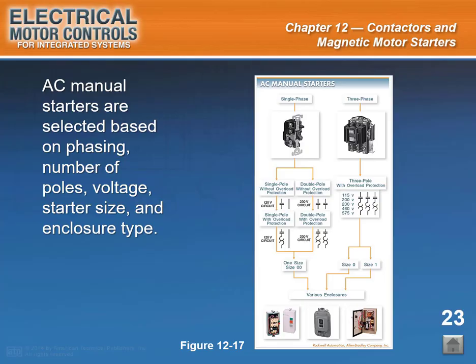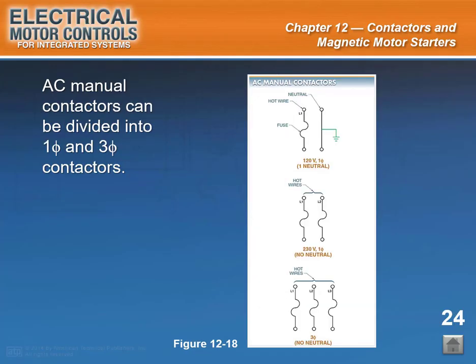AC manual starters are selected based on phasing, number of poles, voltage, starter size, and enclosure type. Starter sizes are given in General Motor Protection Tables. General Motor Protection Tables indicate motor protective device sizes based on motor horsepower, current, fuse classification, and wire size. End of slide 23. Start of slide 24.